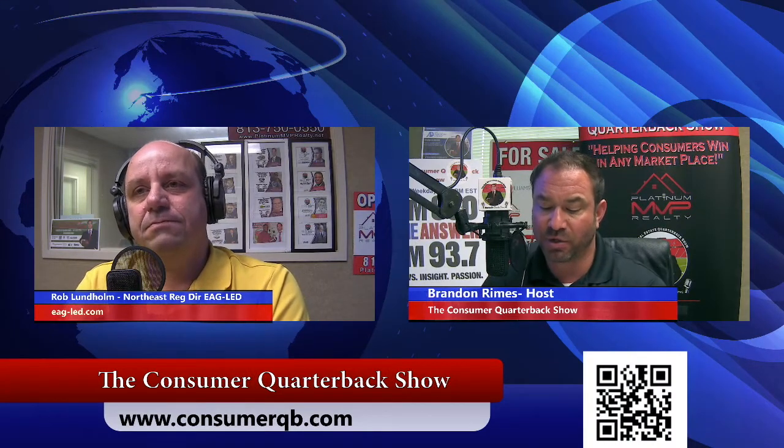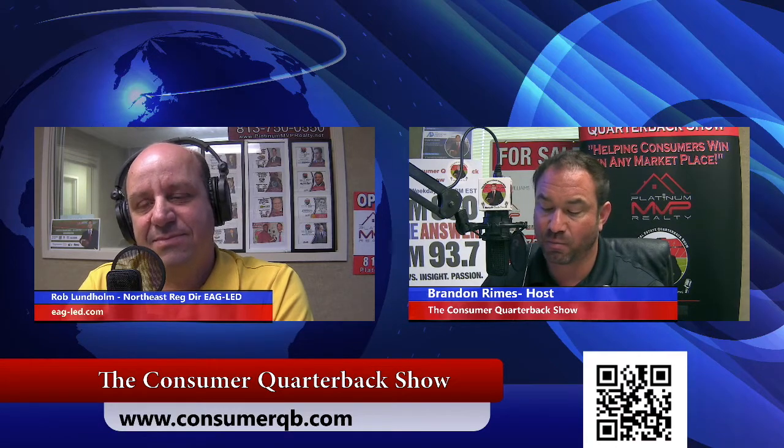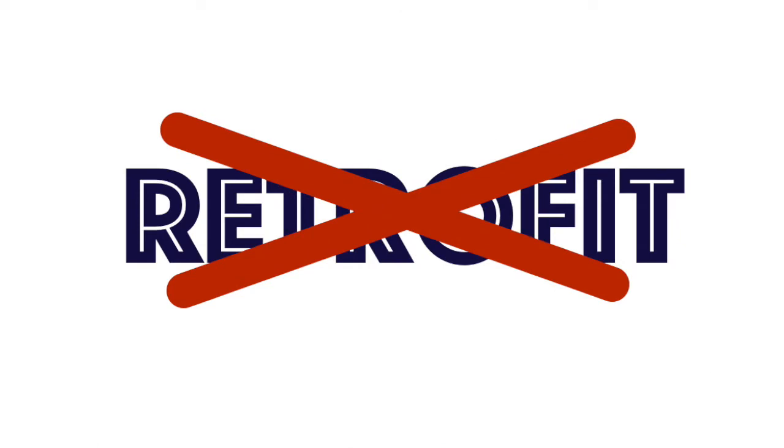And you sometimes hear people talk about retrofitting to save money. What about that? That's our curse word. Yeah, that's a curse word. What happens when somebody does a retrofit, let's say they take a fluorescent fixture like you have in the studio here, and rather than replace the whole fixture with an integrated LED, they have to take the light apart, disconnect the ballast, wire the fixture around the ballast, and then you're putting an LED light bulb in a fluorescent fixture, and it's too much energy for it to be effective.